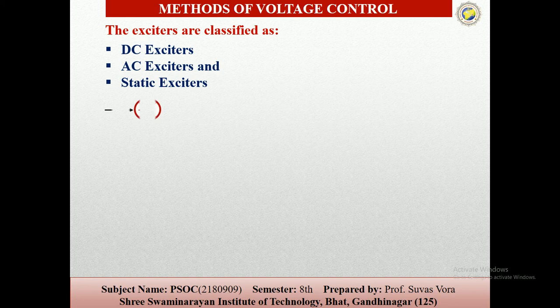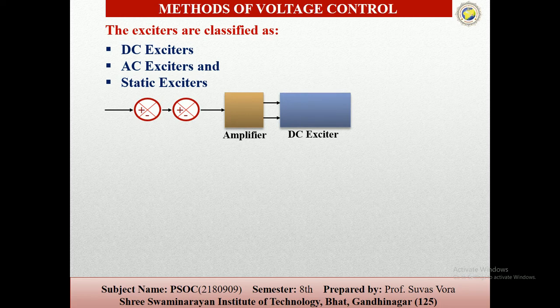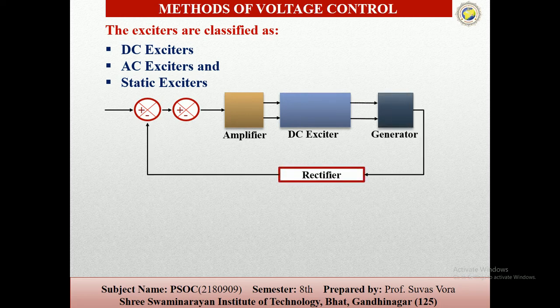So the block diagram, you can see here the block diagram of the generator voltage control system. This one is the signal given to the amplifier, then the DC exciter, then the generator. This one is continuously checked through the rectifier, and stabilization we can put in the DC exciter and the generator. We know how it works.